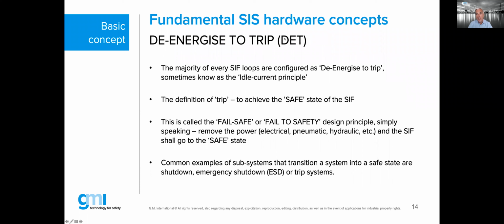I made an abbreviation, and you can say, well, there are many abbreviations available on the market, and I fully agree. But for the sake of simplicity in my webinar today, I call de-energized to trip a DET, or de-energized to trip. And very clearly, it's important to understand that we want to trip the safety function, we want to stop the safety function to go to a safe position. That is the basic principle to understand.